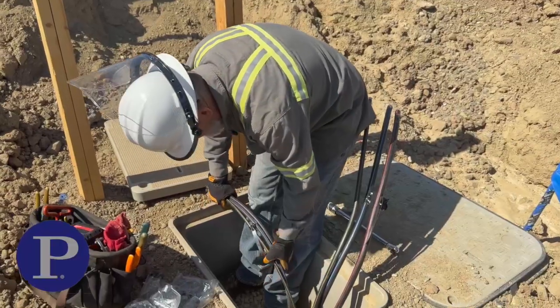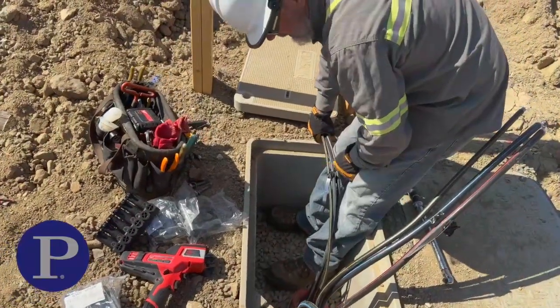This is an illustration of a typical handhole. This is like a 1730, 18. When you pull the cable in, if your ducts are sitting on this side of the handhole, you're going to want to pull your cable up and over to this end of the handhole, and then you're going to make a cut just outside of that handhole on all the cables. If you've got another duct over here, pull the cable up, you're going to want it over here. When these are all made up, we want them to fold over and sit nicely at the end of the handhole.